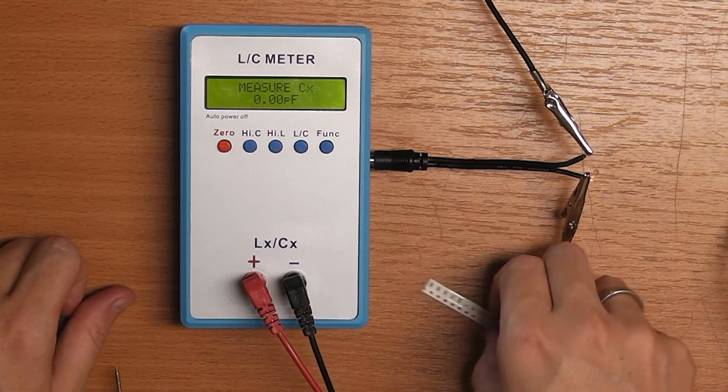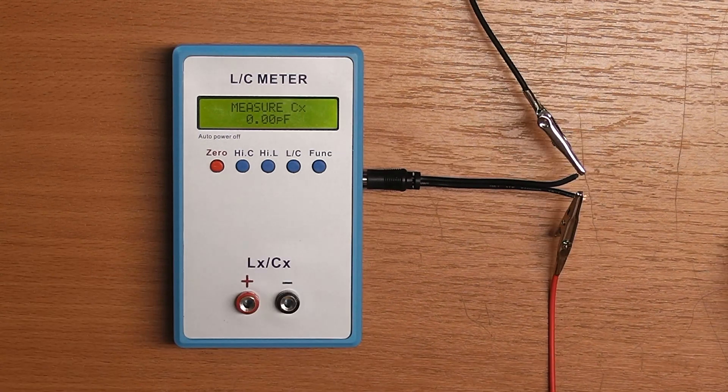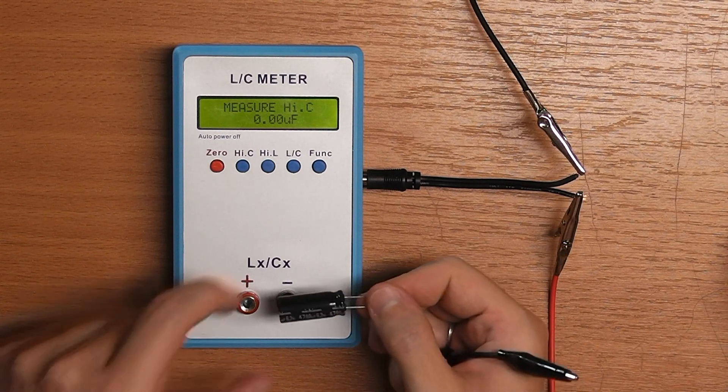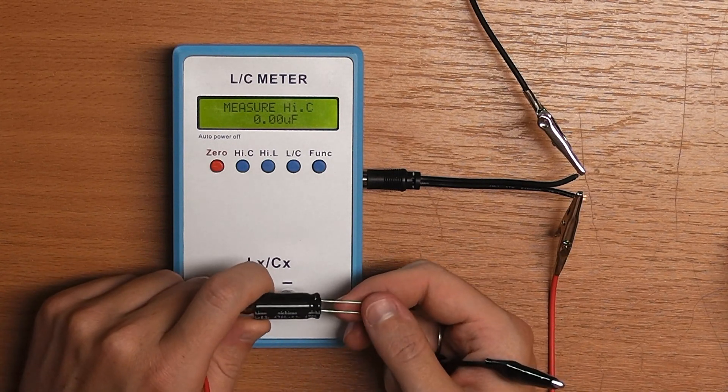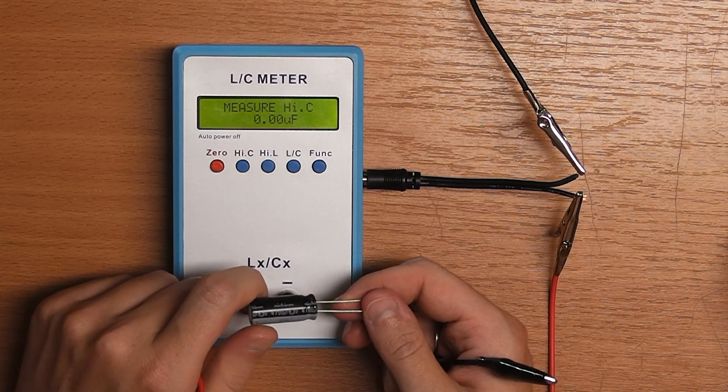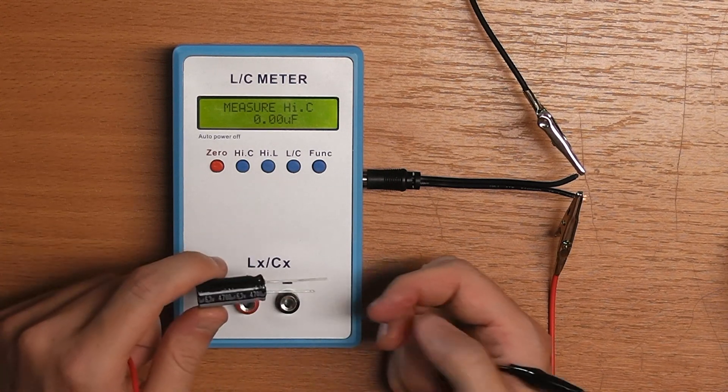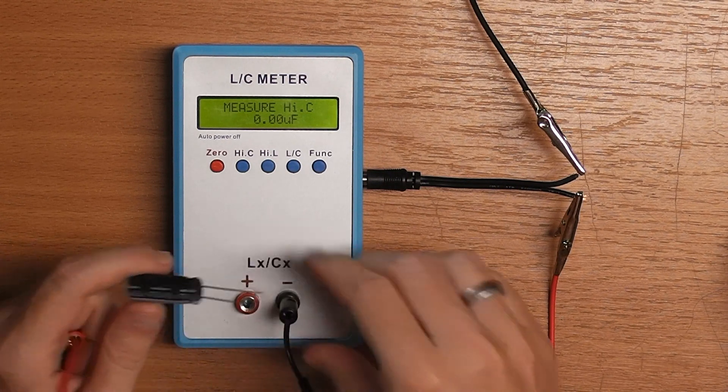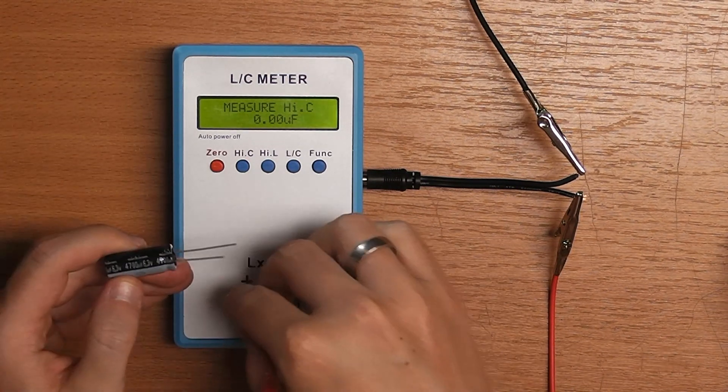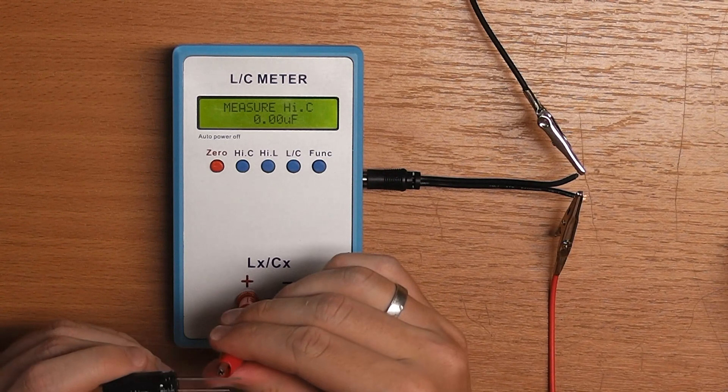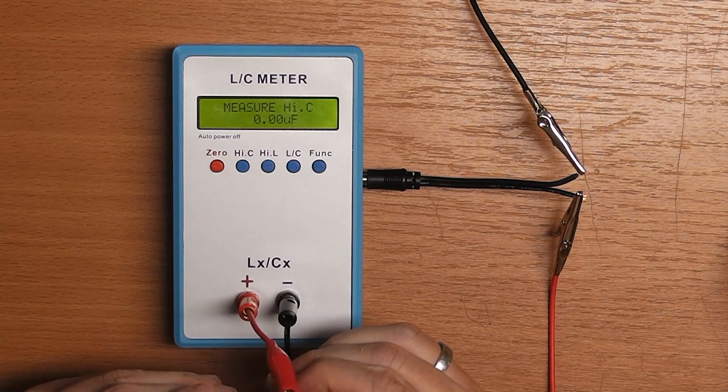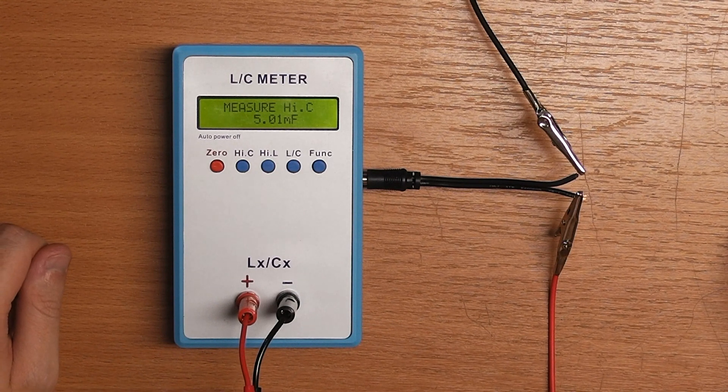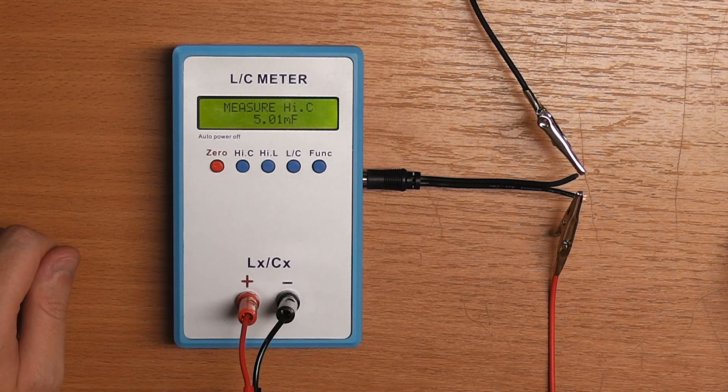I'm going to measure some larger capacitors now. So for this measurement, I'm going to enter high capacitance mode. This is a Nichicon 4700uF, which I earlier measured with a different instrument to have about 4.9 mF. So I'm expecting to see around that value. And it says 5.01 mF. So this is pretty good.